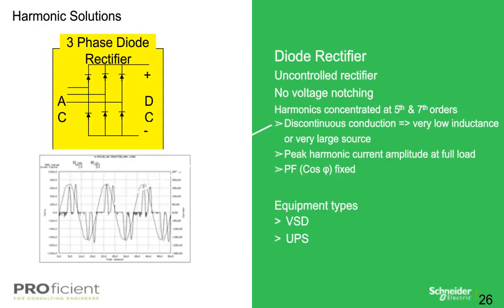Okay, next we'll get into a three-phase rectifier, which is a diode rectifier, which always conducts when the AC voltage is higher than the DC voltage. There are no DPF issues. It typically operates around a PF of 0.98 to 0.95, and the harmonic amplitudes are highest at full load. Percent THDI is lowest at full load. Harmonics are concentrated in the 5th and 7th harmonic order.